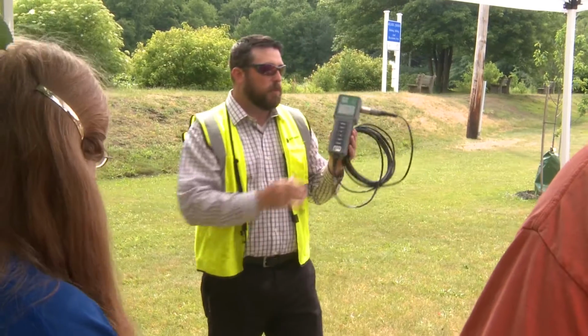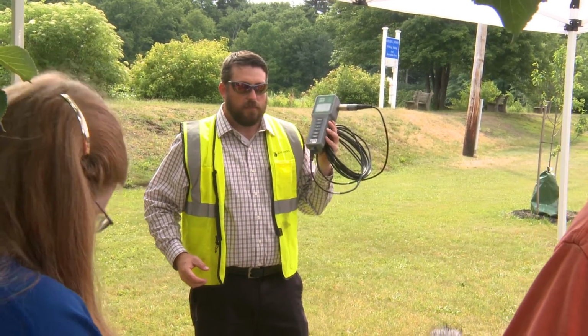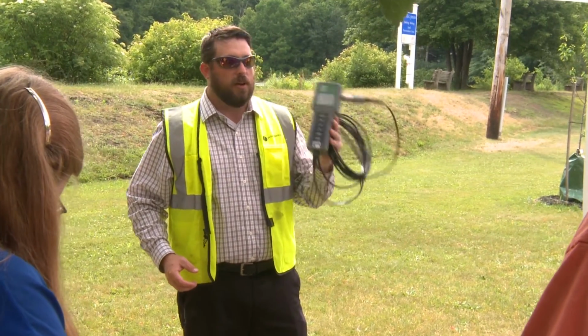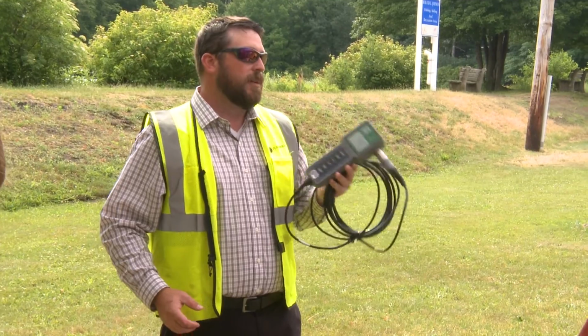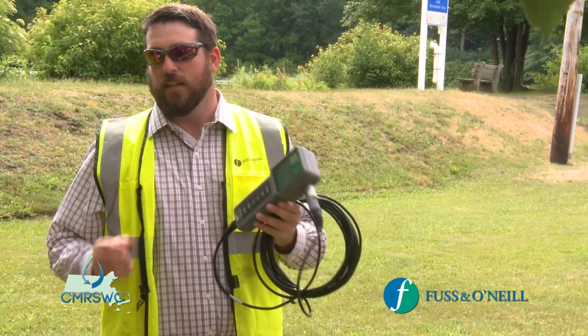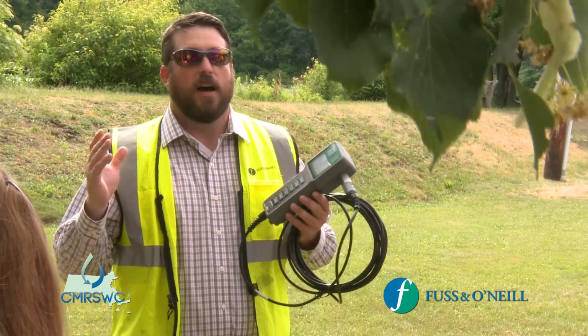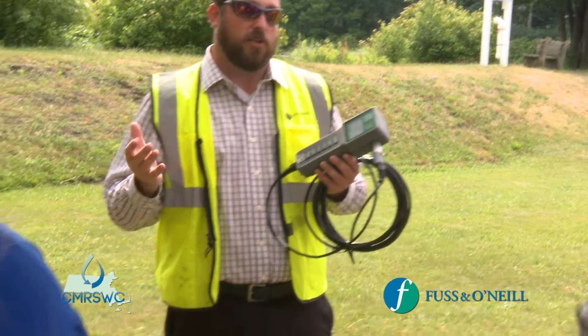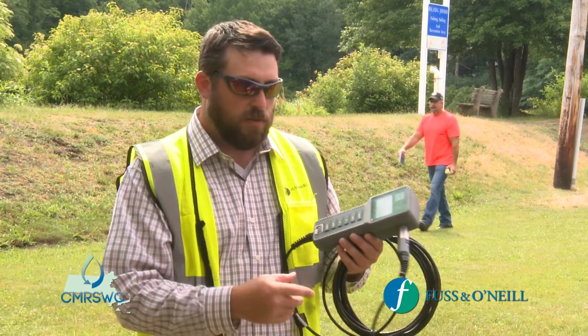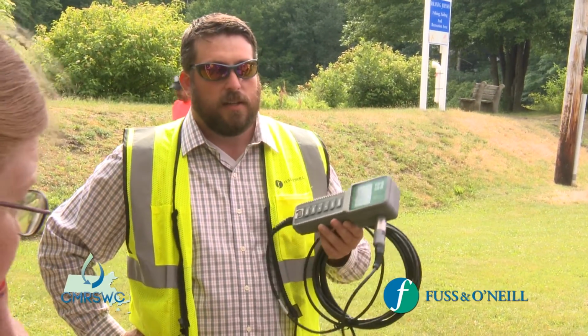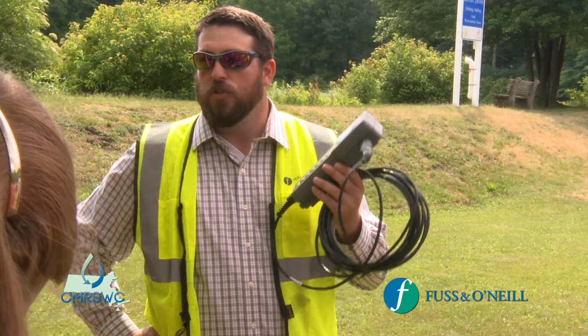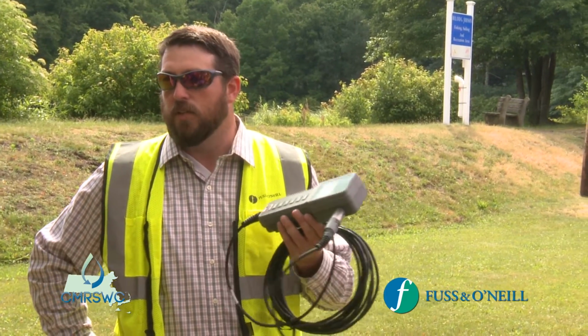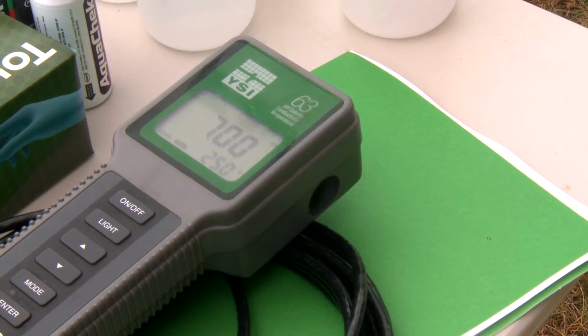So for field meters, has anybody used field meters before? A couple people have. For whatever reason, like all scientific equipment, the longer you leave these things on, the happier they are. I don't know why that is, but that is definitely the case. So you should definitely turn your meter on 20, 30 minutes before you plan on actually using it. It's also helpful, for this particular meter, if you have the manual with you. I've got the manual in the binder there if anybody wants to take a look. But it does recommend that you put this in a calibration standard and let it acclimate to the temperature of your calibration standards before you calibrate the machine.